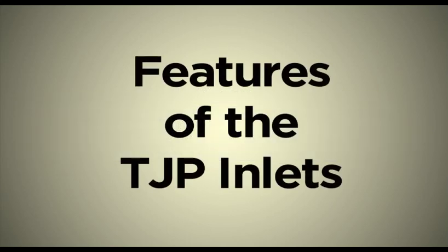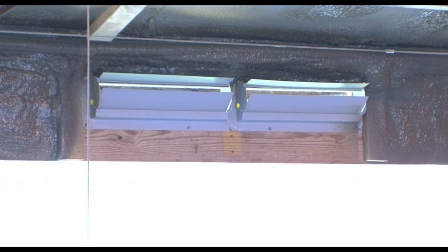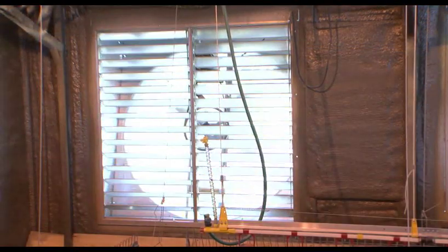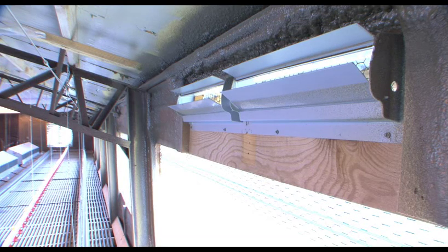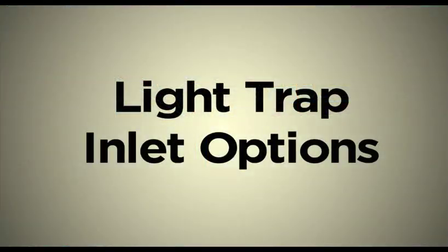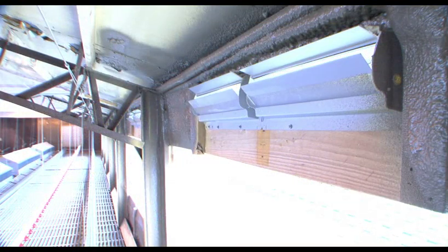Features of the TJP inlets: when minimum fans are on, the lighter weighted inlets open to allow fresh air into the poultry house. When transition fans turn on, both the lighter and heavier weighted inlets open to allow fresh air in. When the house goes into tunnel ventilation, the static pressure will drop and the TJP wall inlets will close. Double L Group offers light trap inlet options that will fit your needs. We hope this video has given you some insight on the installation and use of TJP inlets from the Double L Group.